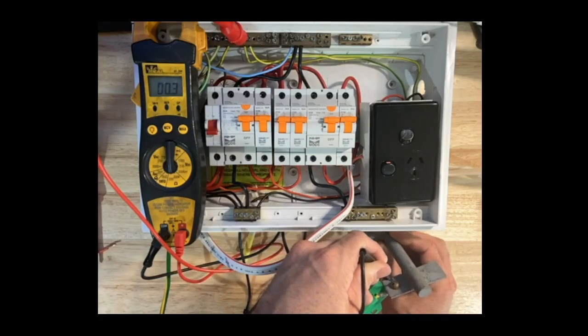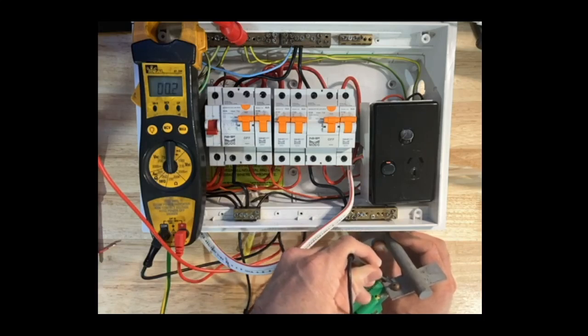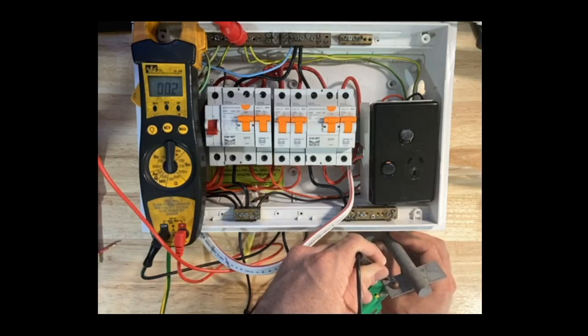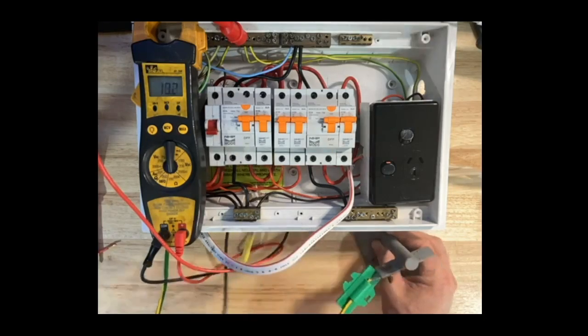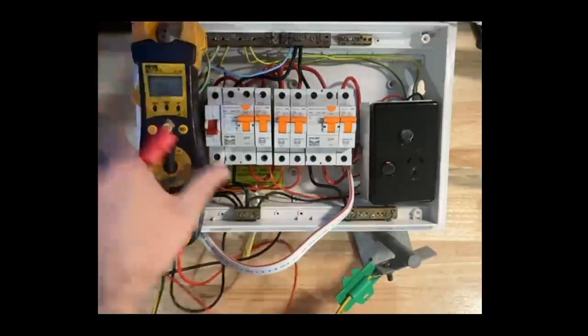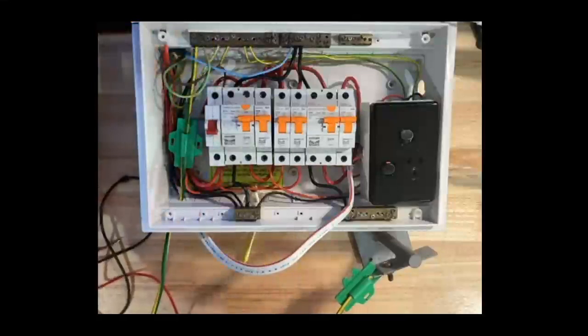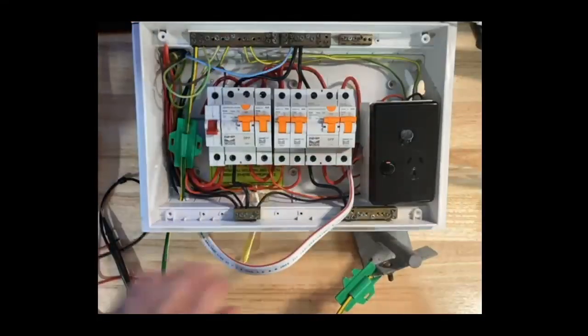It must be no greater than 0.5 or less. You just see that it's switched down to 0.02. So we've got a very low reading there. That's fantastic. My main earthing conductor in this case is good. It should be good because I can see the whole thing. It's a nice big 6 mil and it's only very short. So we should have very little resistance in that circuit.